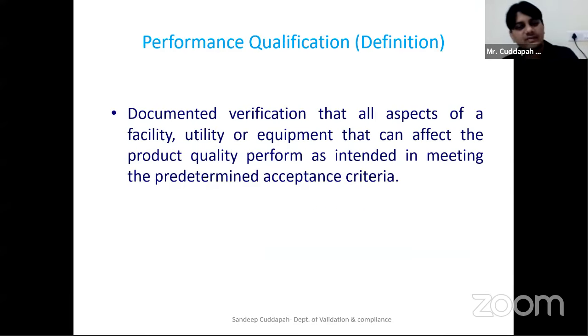Then it comes to performance qualification. This performance qualification will be verified by all the regulatory bodies, because that is the core part of your equipment. Once your installation, operation, everything is done, during your performance qualification, you will establish certain settings or set points, so that those settings or set points will actually be used for your manufacturing process.